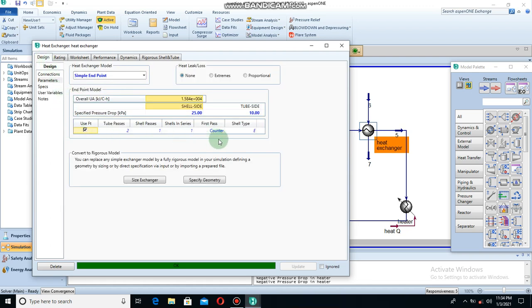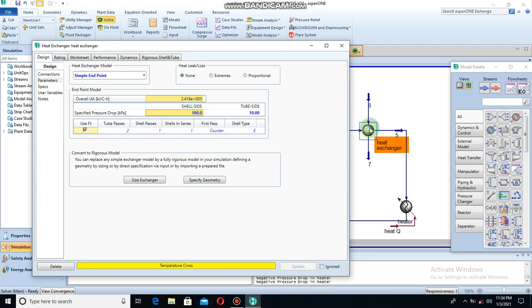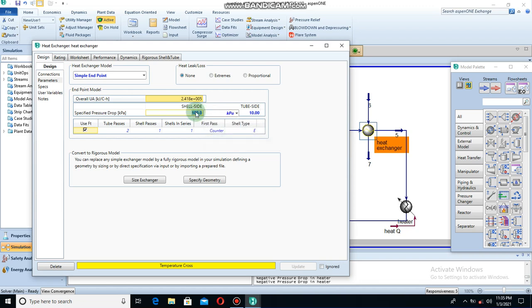I also told you that the pressure drop matters. Let me give this a higher drop in pressure — and we have a temperature cross once again. So this is what I was telling you about: the pressure matters, the drop in pressure matters, the temperature matters, the phase matters. These are the simple ways to get the temperature cross out of the system.